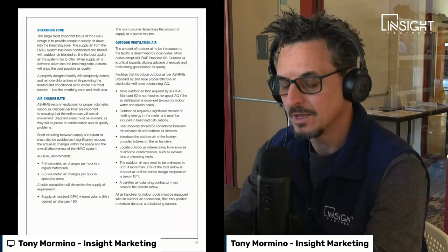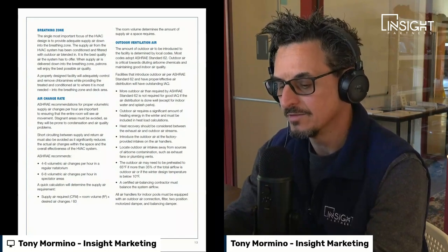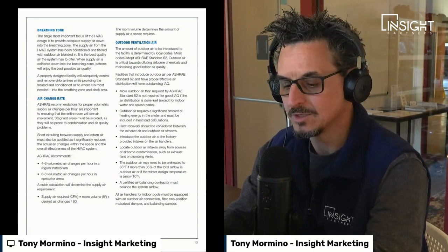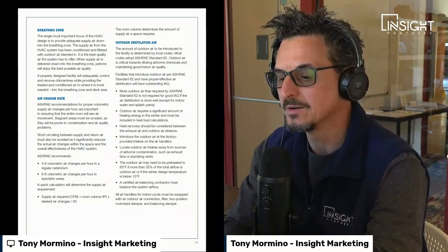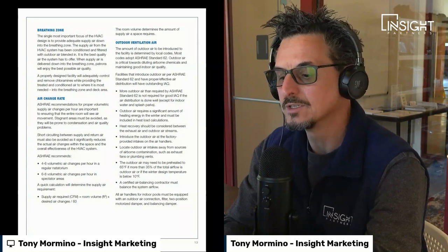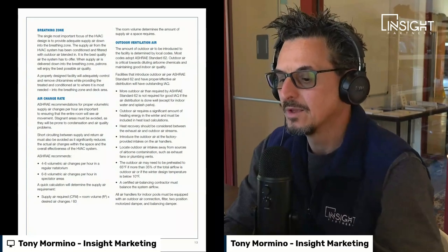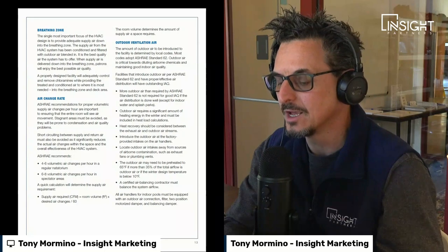A quick calculation will determine the supply air requirement: Supply CFM = Room Volume (cubic feet) × Desired Air Changes ÷ 60. The room volume determines the amount of supply air the space requires. Regarding outside air ventilation, the amount of outdoor air to be introduced is determined by local codes — most codes adopt ASHRAE Standard 62. Outdoor air is critical for diluting airborne chemicals and maintaining good air quality.